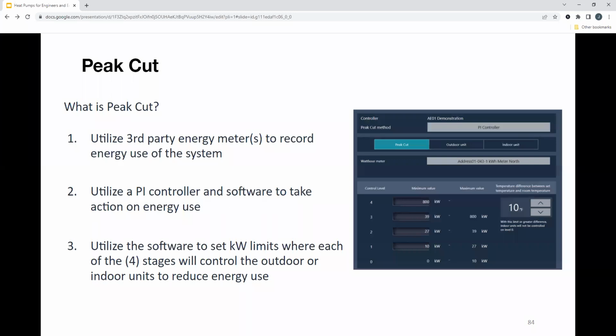You're able to organize peak cut, and what that is, is saying, I'm not trying to use over 800 kilowatts this month. I want to stick below that point. So halfway through the month you can set a limit: 750, 700. What that does is adjust the outdoor temperatures and the indoor temperatures accordingly to save a little bit of energy so that the compressor is not working as hard, right? So you have control of that. You do need to utilize your pulse input controller and the software that's associated with the energy allocation setup, right? So you can set four different stages with kilowatt limits associated with your building.